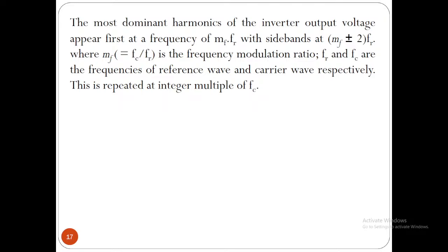So in sine-triangular PWM modulation, if you select a particular carrier and reference wave frequency, all harmonics up to that value are eliminated, and the first appears at a frequency of MF plus or minus twice FR. This is a well-established, common phenomenon, and multiples of that frequency will appear again. This is the standard practice in PWM technique for harmonics elimination.